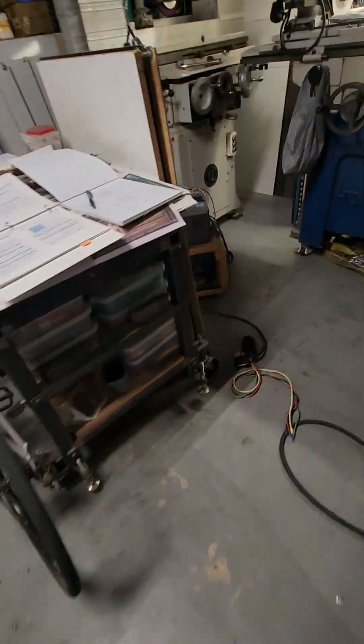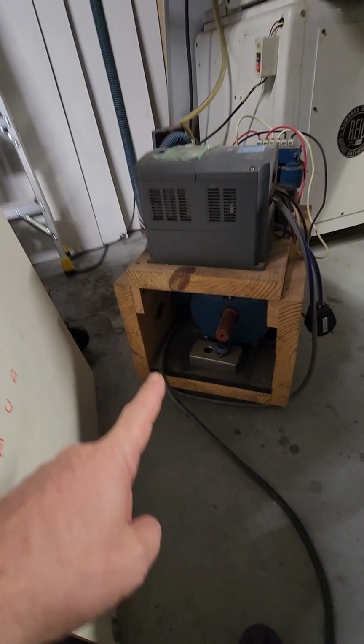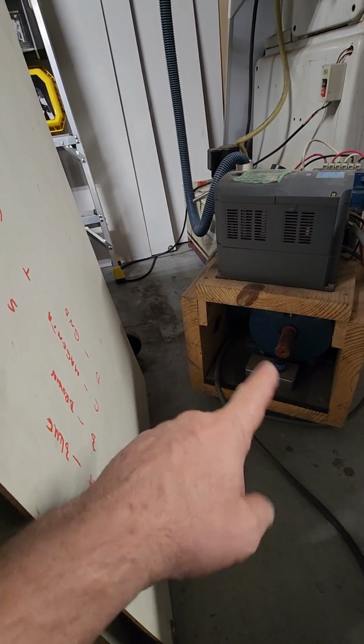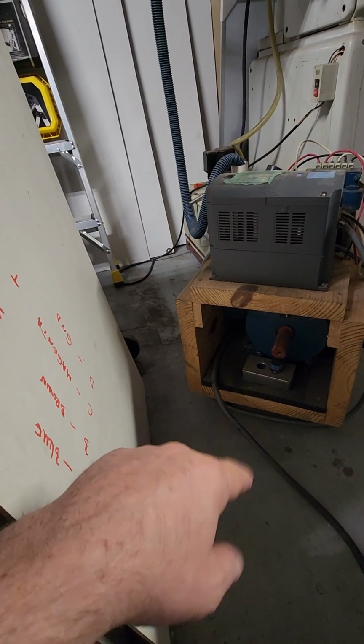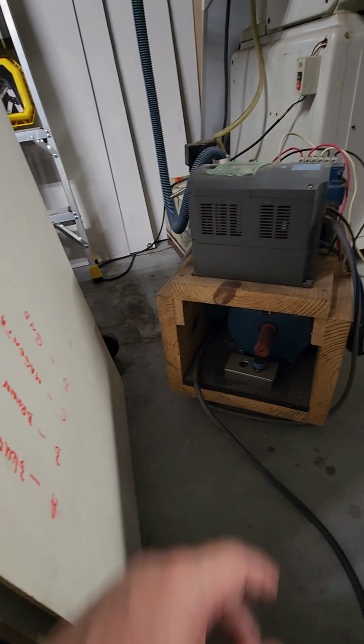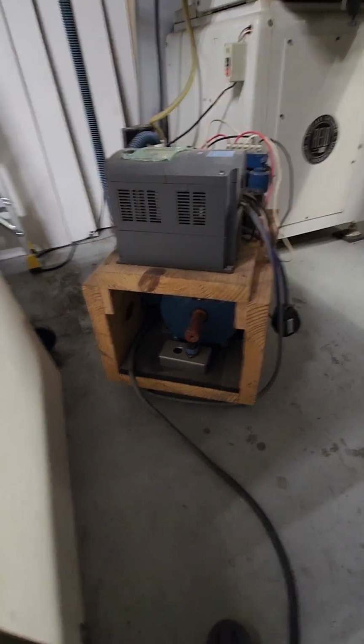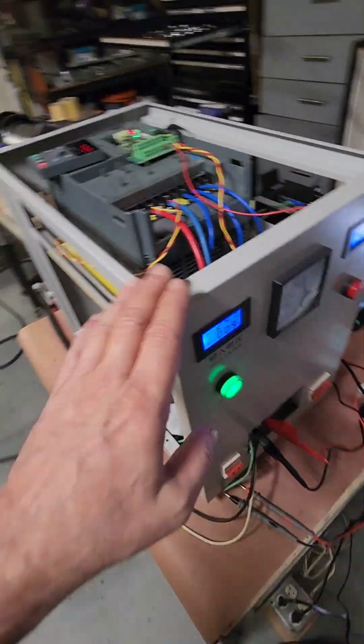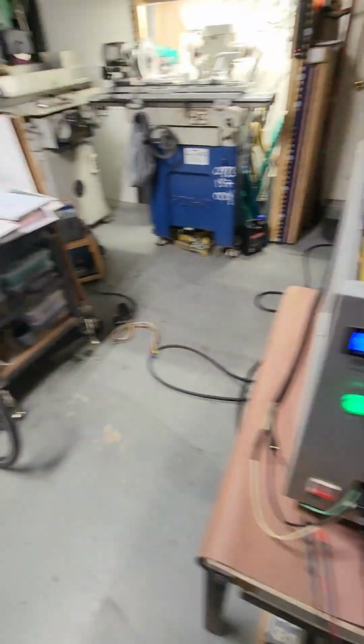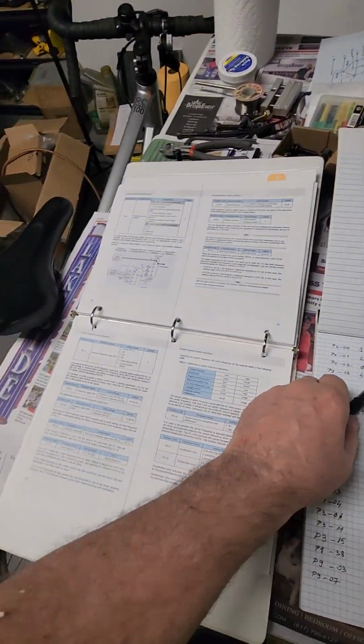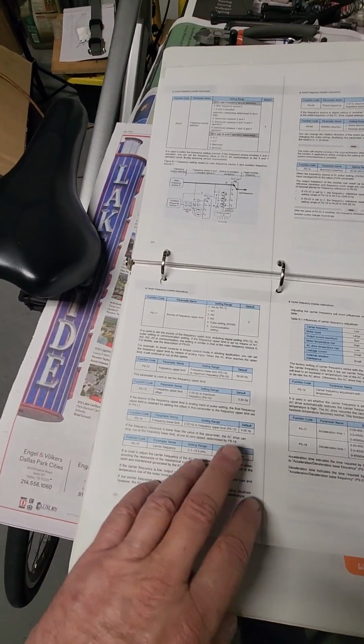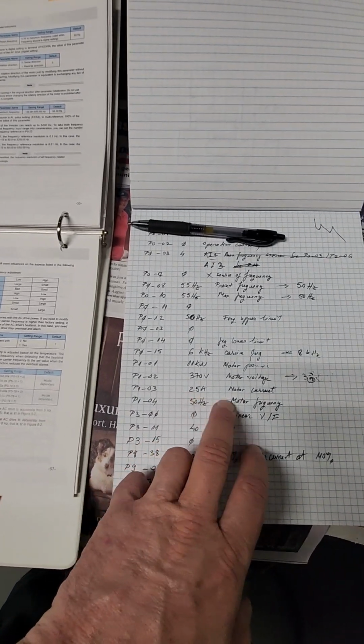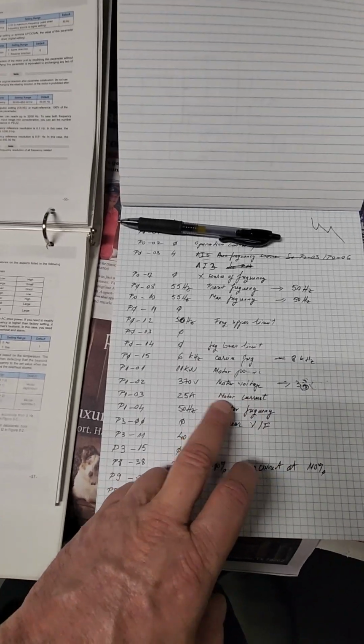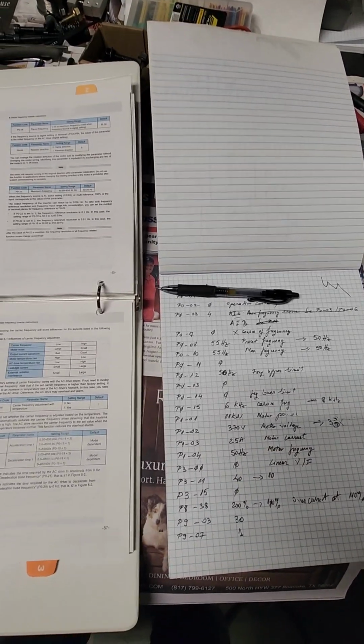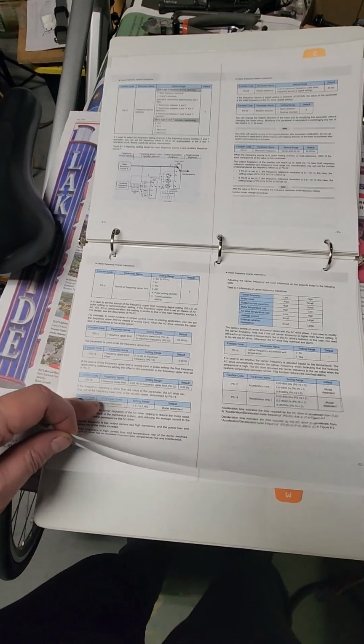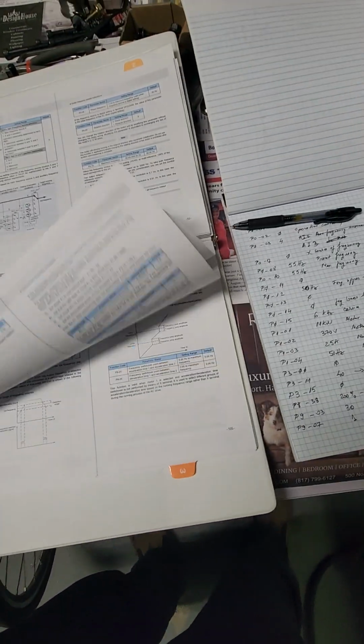Also, I mentioned I'll use this motor, but it's wired for 220, so I have to take it out from there and reconnect the terminal for 415 or whatever. I think it's 400 volts to do that. So yeah, I think this will work. I need to find in the parameters where you control the max current. I mean, there is a current here you set for your motor, but that's just the RMS, the average. You need to find where you set the peak current, which will protect this drive. It's lots of parameters.